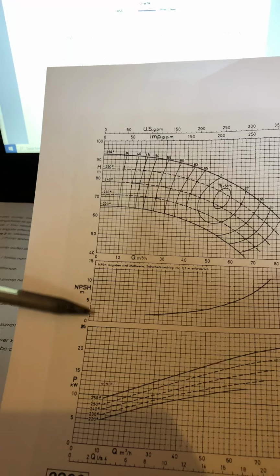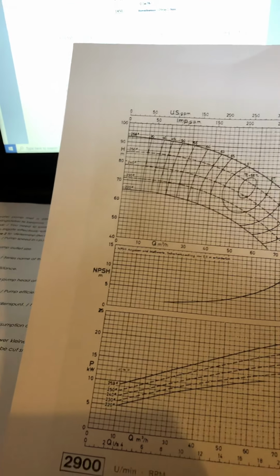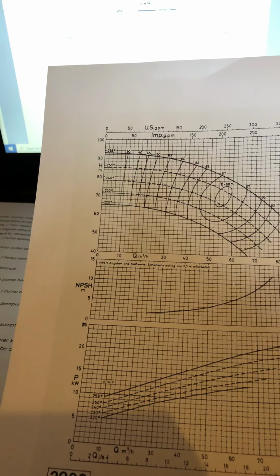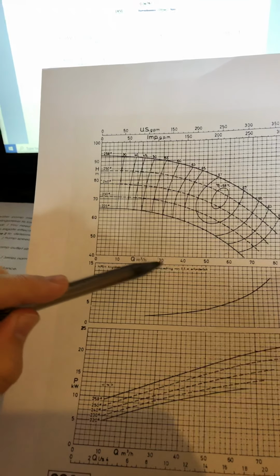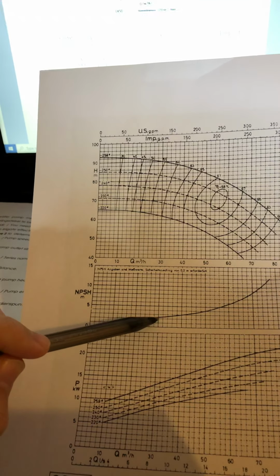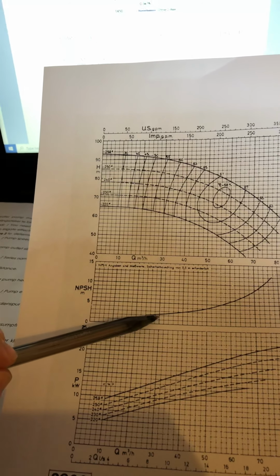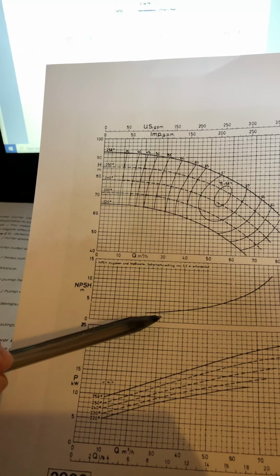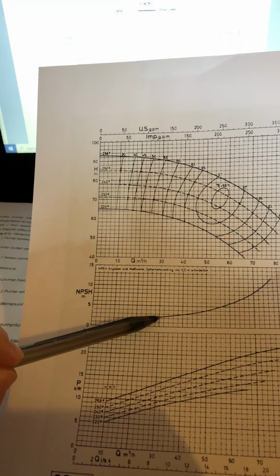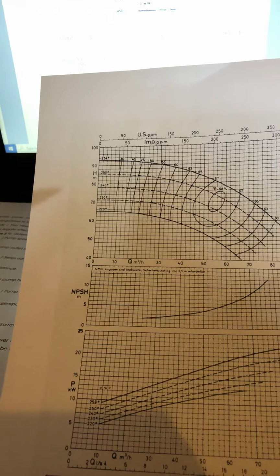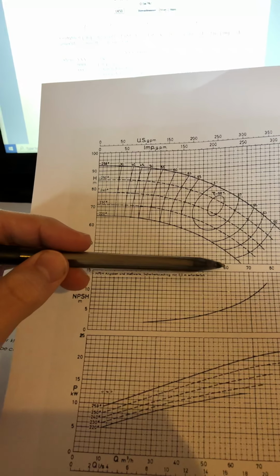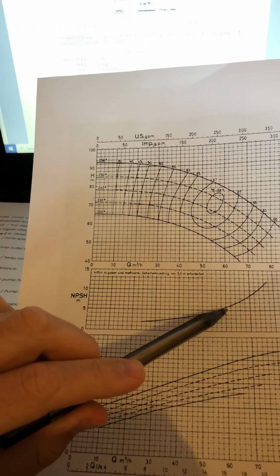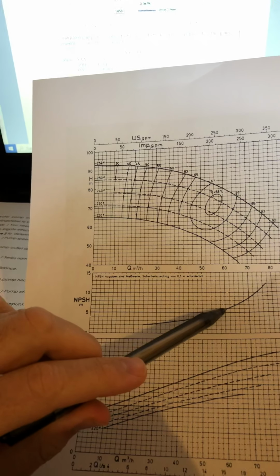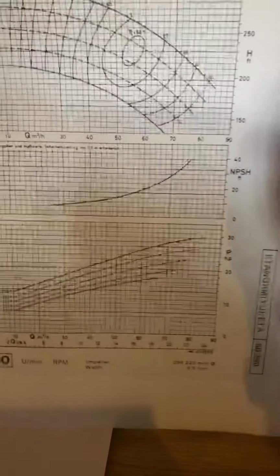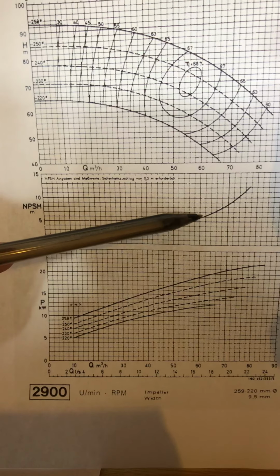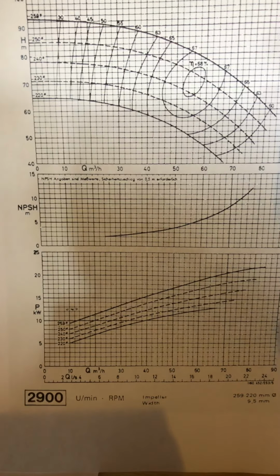Next is going to be this one in the middle. NPSH stands for net positive suction head at duty point. Because you are still at that 30 cubic meters per hour, you are cutting this graph right over there. And so you know that the net positive suction head, where this line cuts that curve, is going to be 2 meters. If, for instance, you had 60 cubic meters per hour, then you would be on this line, and your net positive suction head would be 6. So if you take 60 and you were there, then you'd walk back and find 6.